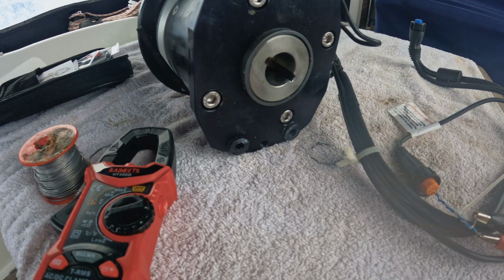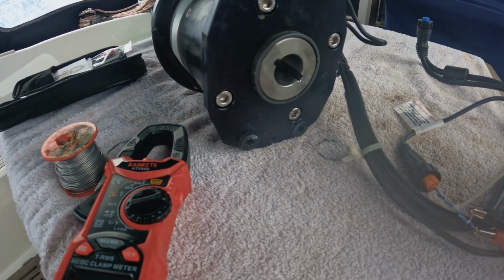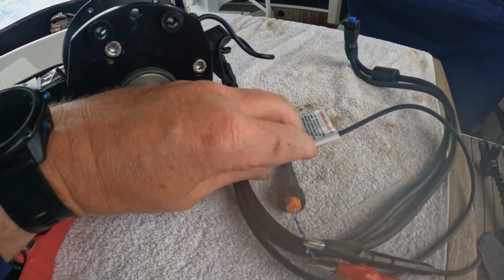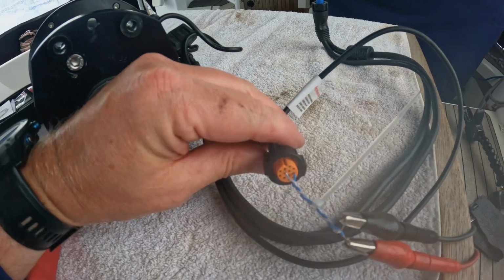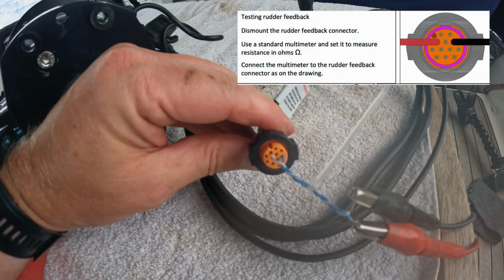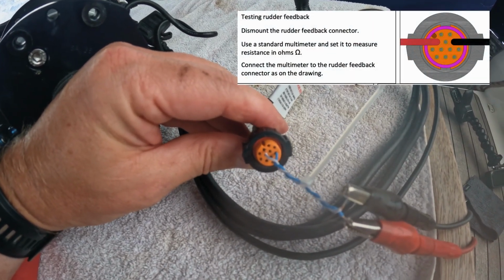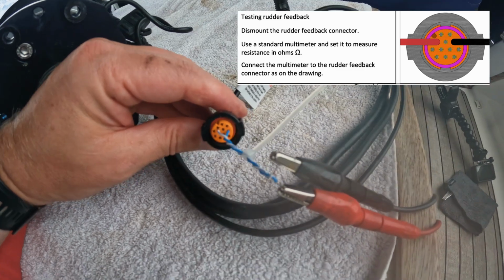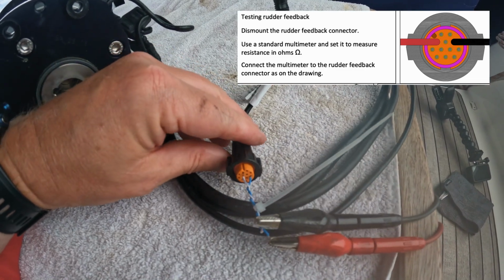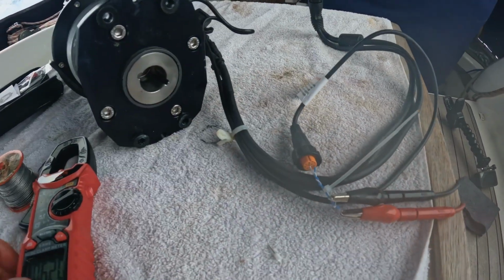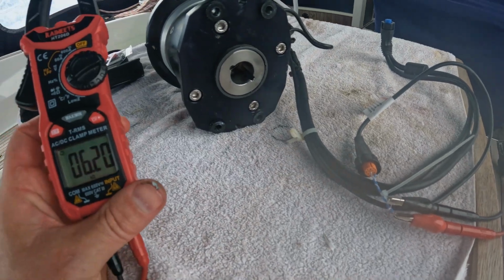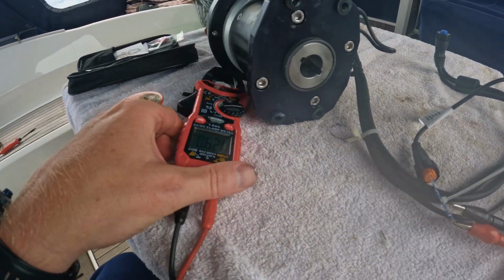So what we're going to do is test the transducer, the feedback transducer. I've wired across the appropriate terminals here, put a couple of bits of wire in, and then connected the meter across it. Currently we're reading 6k.